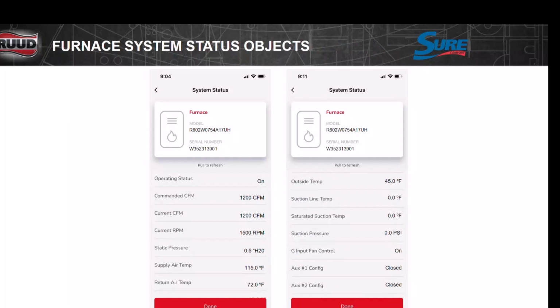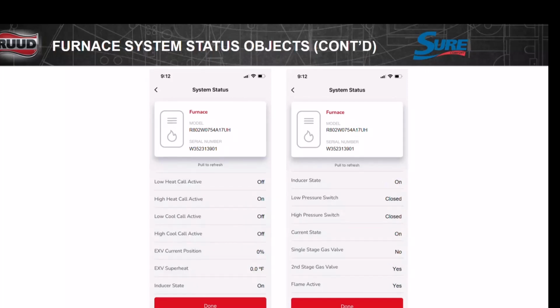As you can see, it tells us our supply air temperature, our return air temperature, so it's taking that split for us to tell us our heat rise. And then we have a place for all of our sensors and everything to hook up. And there's our auxiliaries there. That's our flip switches. And it'll tell us if we have an active call on cool or heat, whether it's high or low. It tells us our inducer's running. So how many times are you going to have to go up there and listen to see if the inducer's coming on? No, not anymore. You go to the thing that tells you the inducer's running.